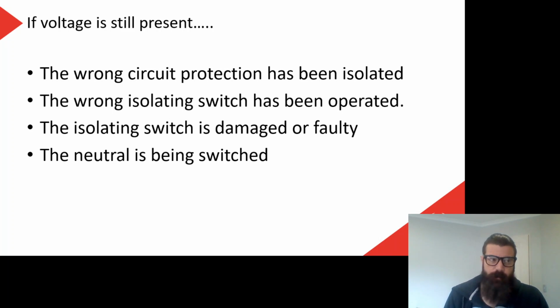Or the neutral is being switched, which if you do all those other things and you're certain that you have isolated the correct thing and you're still finding voltage there, then we may have a switch in our neutral, which is a fairly serious problem that you're probably going to, at least while you're a trainee, need to get somebody else to help you with, because something has gone terribly wrong. I have come across that a couple of times, so we were switching the neutral instead of the phase, and in one particular instance I was asked to come in as an expert on an accident investigation, because someone had received an electric shock, and we found the cause to be the neutral was being switched rather than the live. So when he'd isolated it, we still had some voltage, and he didn't pick that up and got a shock.